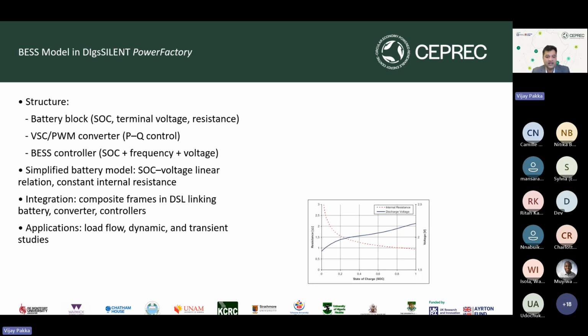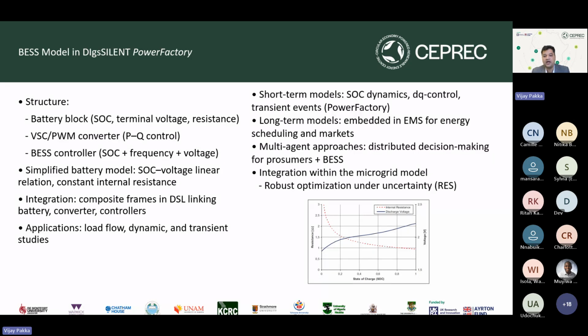There are mainly two challenges with the battery problem. The first is to get a model that is not too complex, but accurate enough. The second is to get the parameters from manufacturers or our own measurements needed for the model. Experts in other work packages are working on this, and in collaboration with them we try to bring these models onto the electrical model of the microgrid, since only a model with good, appropriate parameters can deliver good results. So we look at characterization by the capacity of the battery, internal impedance, open circuit voltage, self-discharge, and so on.